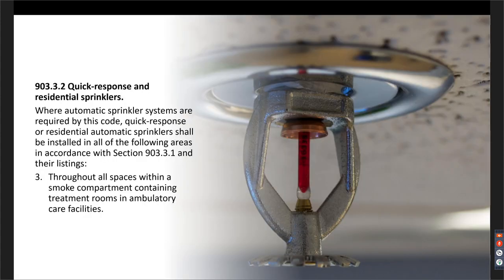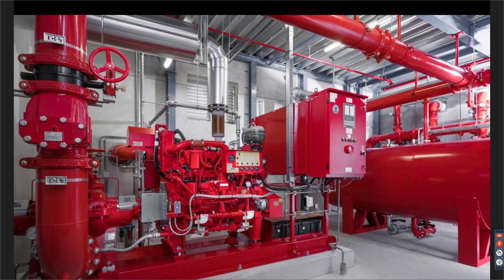And a little bit of a side note, for light hazard occupancies, which would include I-2.1s, and specifically for ambulatory care facilities, 903.3.2 requires quick response or residential style sprinklers to be installed. So these are not your standard response or standard spray sprinklers. These are required to be quick response, which is pretty commonplace. Of course, when you have sprinklers and sprinkler systems, you sometimes get a bunch of other things that are associated with it. There are things you might need to be aware of and design accordingly. Do you need a fire pump for your facility? Do you need on-site water supply? Where do you put your sprinklers? Or when you design your sprinklers, how are they located in relationship to other obstructions?